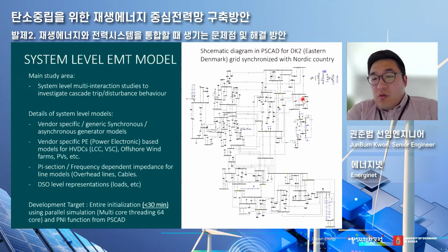Another point I'd like to make is about TSO. I believe KEPCO does not separate TSO from DSO, but in Denmark there's a separate organization for DSO. DSO is building a lot of PV power, and when there's a trip or fault, depending on scale, it can also have a lot of impact on TSO, creating oscillation or tripping some protection relay. So we need to include DSO in our simulation model to improve accuracy.